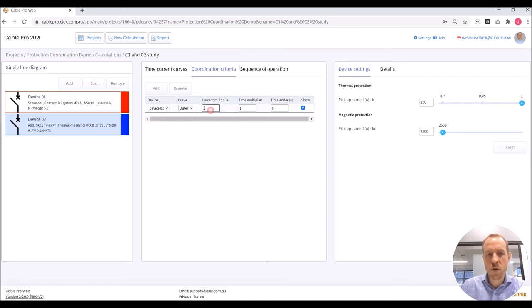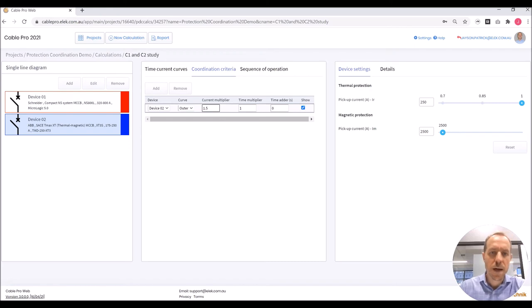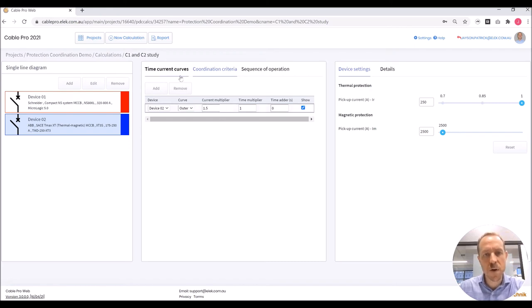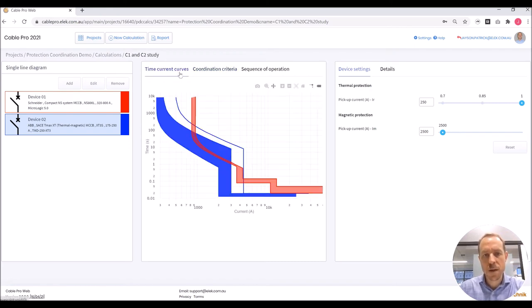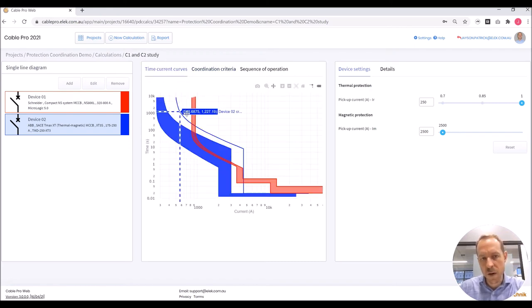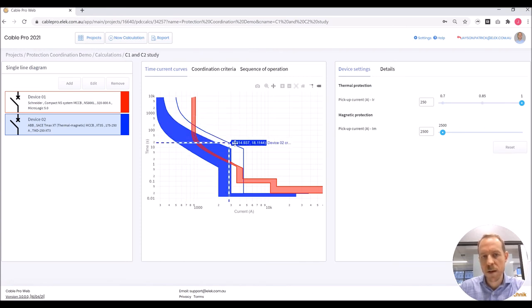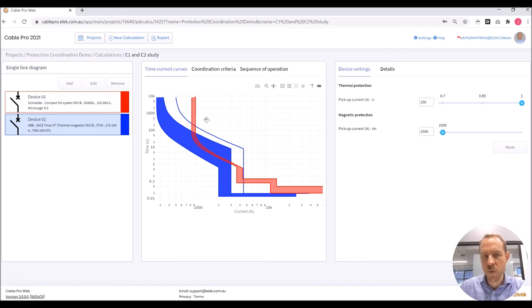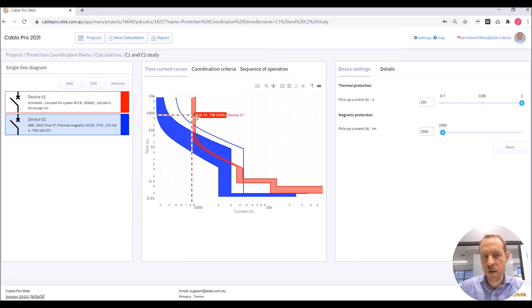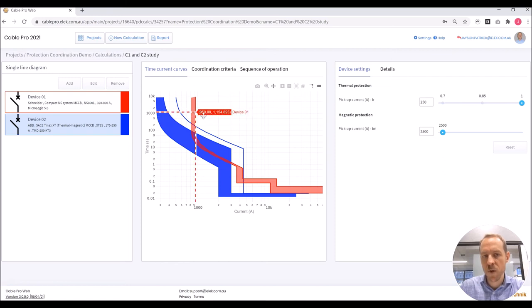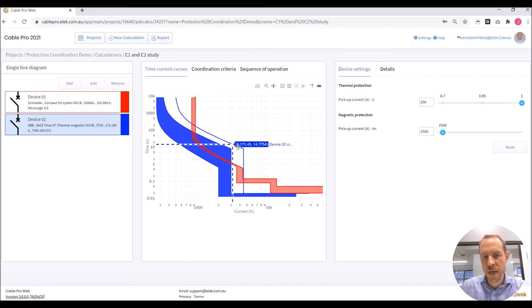So for device 2, I'm going to add a current multiplier of 1.5. And you will see that there is now an imaginary blue line shown on the plots. Basically to achieve coordination, we need to move the curve of the upstream device shown in red to the right hand side of this imaginary curve. And we do that by changing the settings.